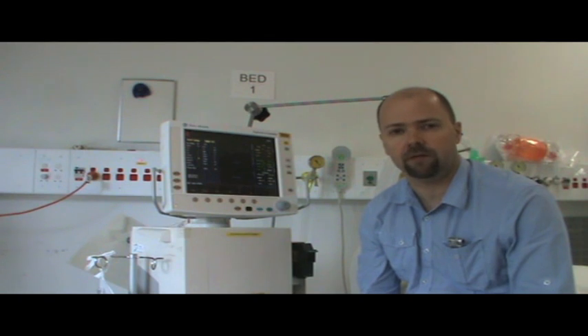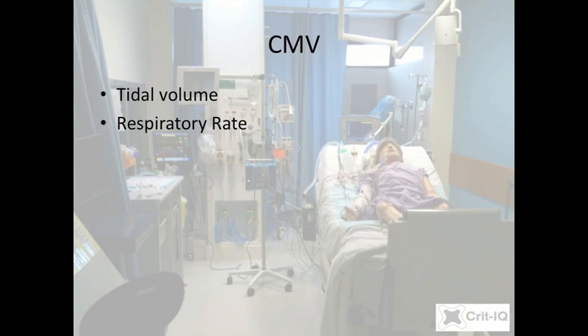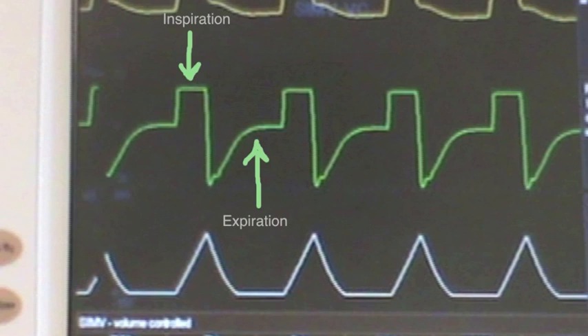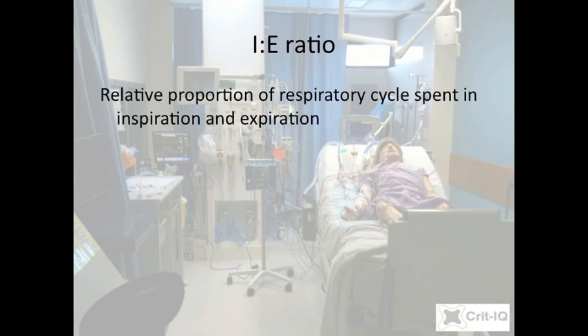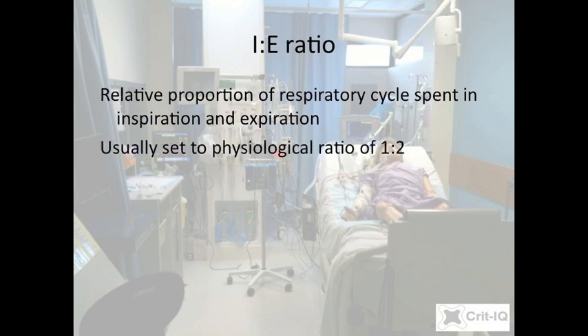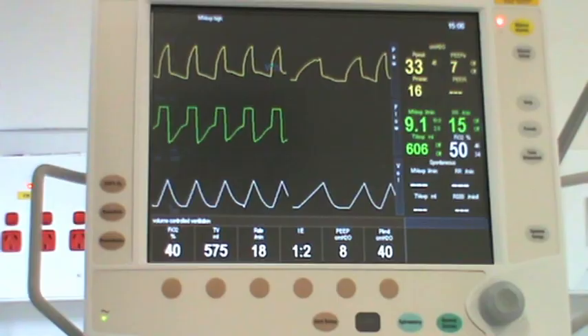The simplest mode of mechanical ventilation to understand is controlled mandatory ventilation, or CMV. This is a volume-regulated mode involving a fixed volume of gas delivered at a fixed frequency known as the respiratory rate. Once the ventilator has delivered the fixed volume, it opens its valves and allows passive exhalation to occur. The relative time spent in inspiration and expiration is set by the IE, or inspiration-expiration ratio, defaulting to roughly normal human physiology — a ratio of 1 to 2 or 1 to 3.